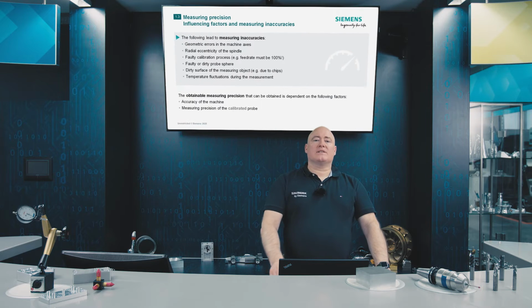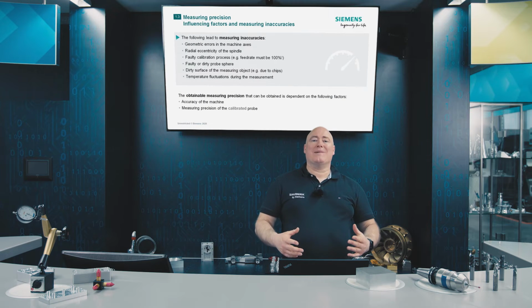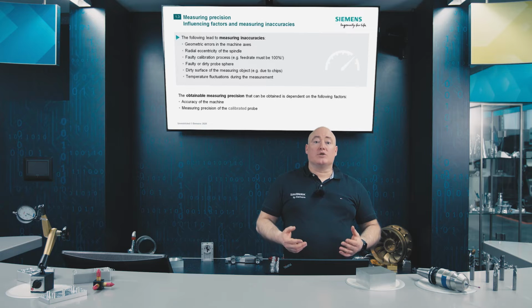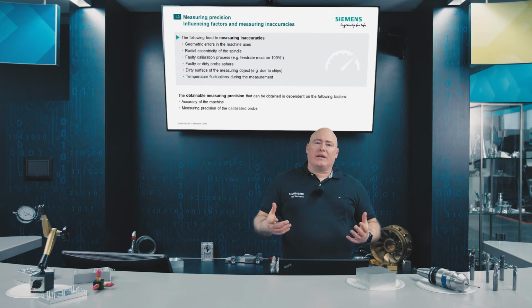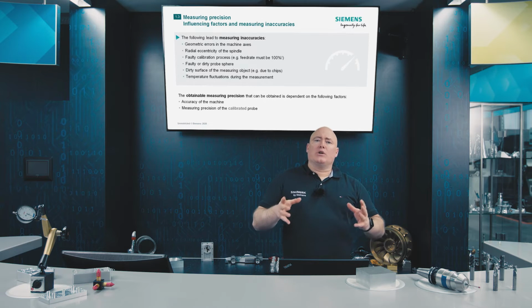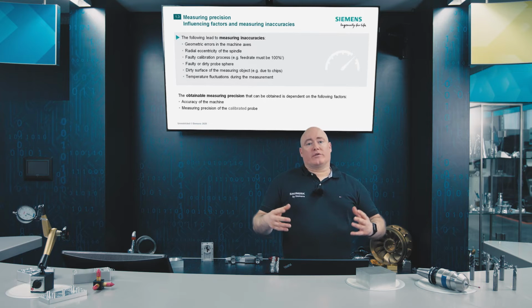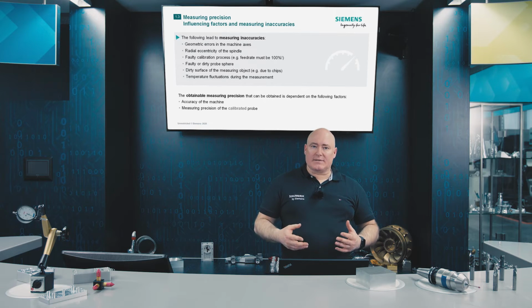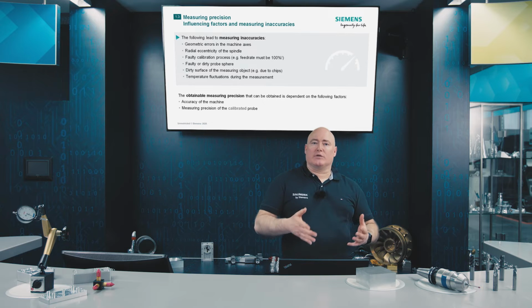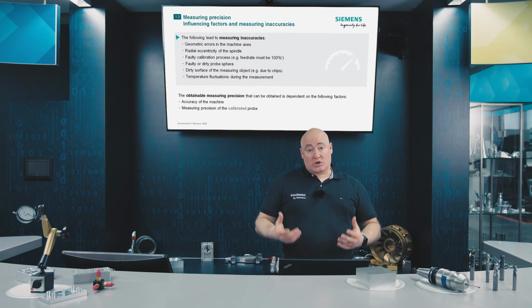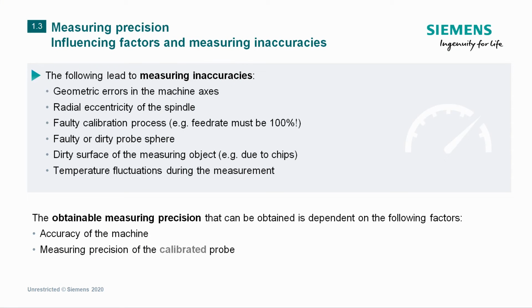Although the measuring instrument has been calibrated, measuring inaccuracies can still occur. For example, there can be geometry errors in the machine axes, radial eccentricity in the spindle, temperature fluctuations or contamination of the item being measured caused by swarf or residual cooling water, for example. In other words, measuring accuracy depends on the accuracy of the machine and the measuring accuracy of the calibrated measuring instrument.